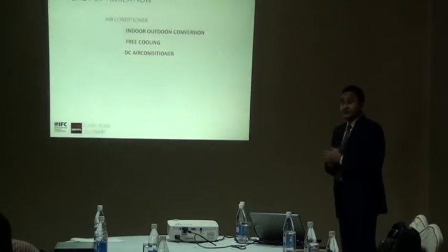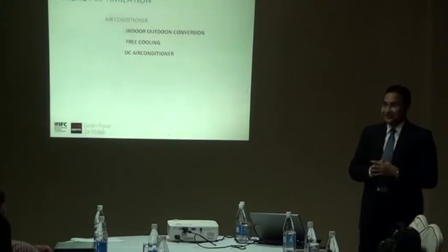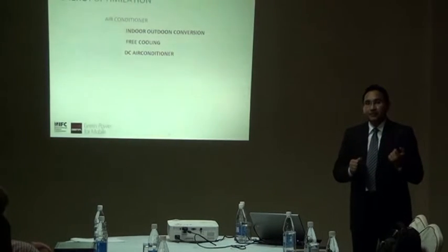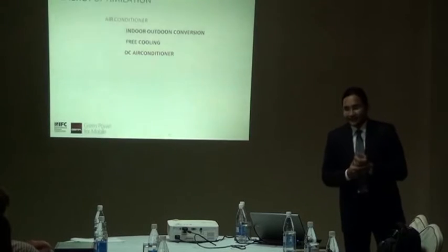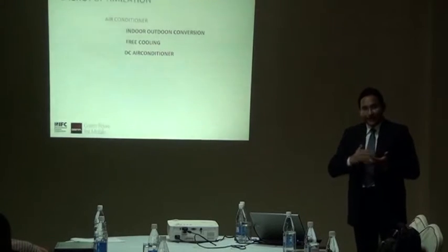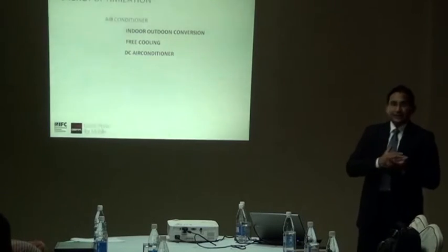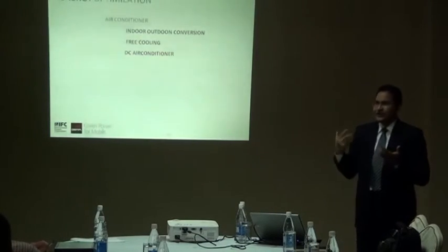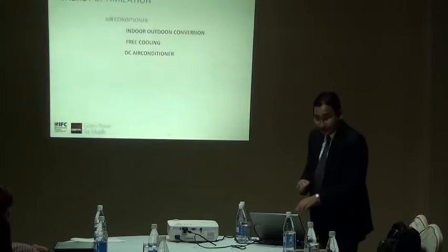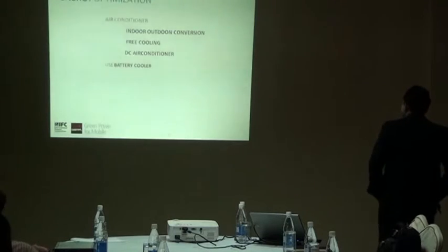Now, DC air conditioner is another good answer. DC air conditioner is not a very common solution deployed in telecom. We have seen DC air conditioners start being deployed, but the number of deployments has been quite limited. I guess it's simply because the free cooling unit got good traction, and free cooling deployment happened quite significantly. And then the second part is the network swapping from indoor to outdoor. This swapping happened in quite a big number. So the DC air conditioner didn't get much traction, but it is one of the solutions. So yeah, this is looking at energy optimization on the air conditioner part.